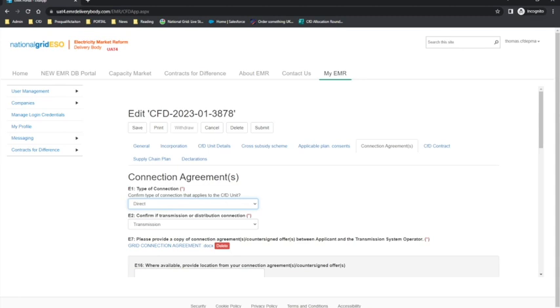Where a direct connection applies to the relevant CFD unit, a copy of the connection agreement must be provided which allows for connection to the relevant transmission or distribution system. Where a partial connection applies, the applicant must provide a copy of the connection agreement, and if the owner of the CFD unit is not the owner of the private network, a copy of the private network use agreement is also required. Where an islanded CFD unit connection applies, a statement confirming that no direct or partial connection currently exists or will exist in the future is required, and if the applicant is not the operator of the private network, a copy of the private network use agreement is required.